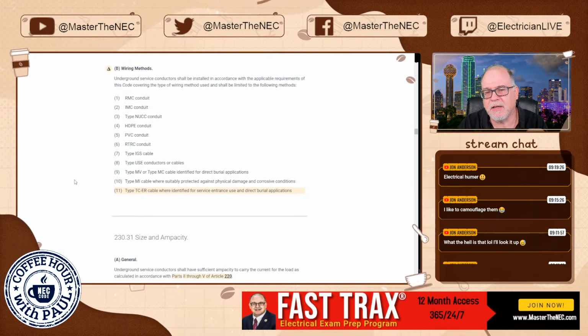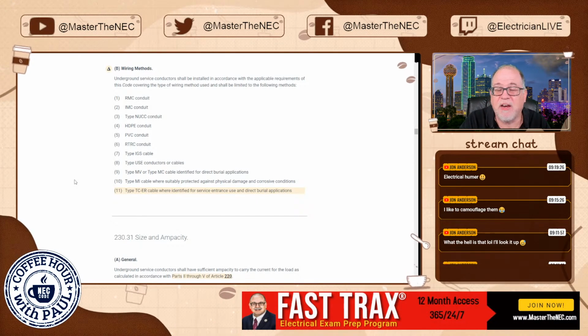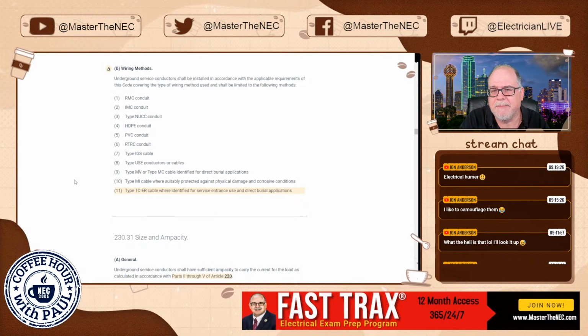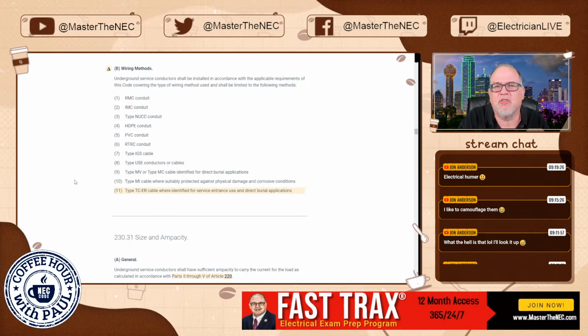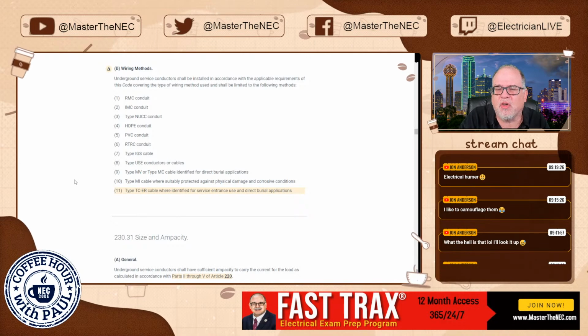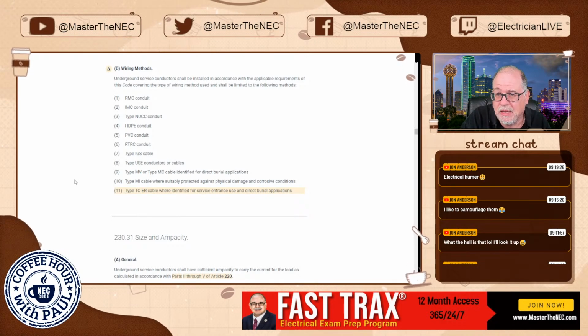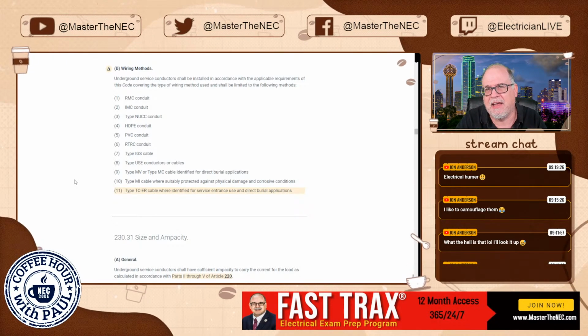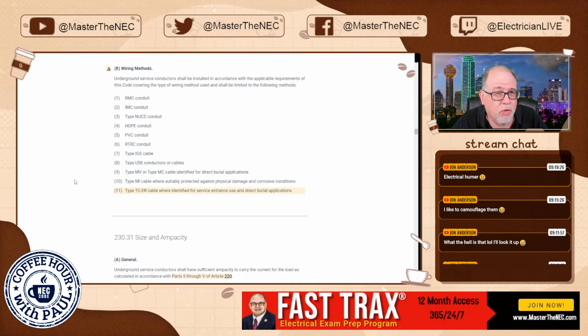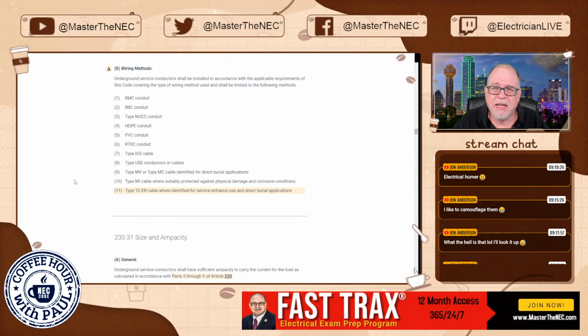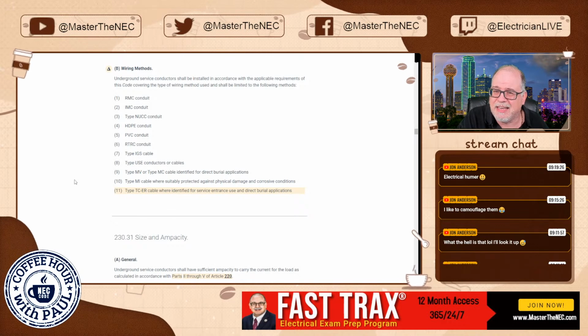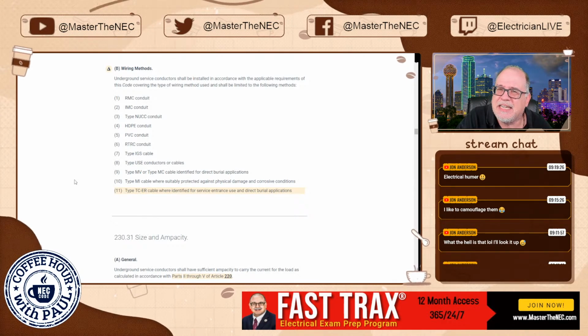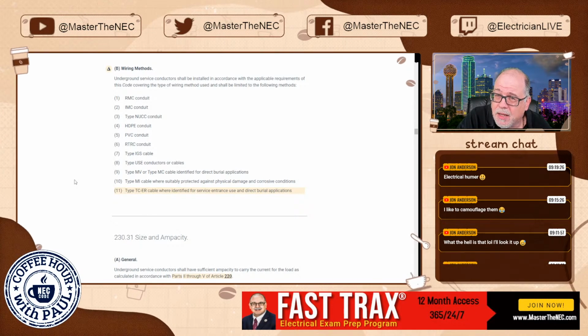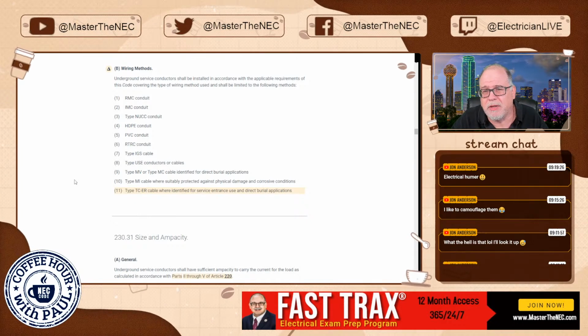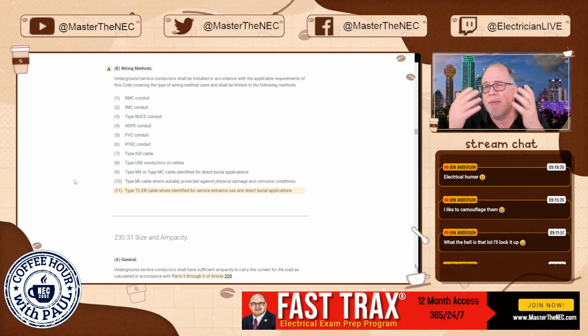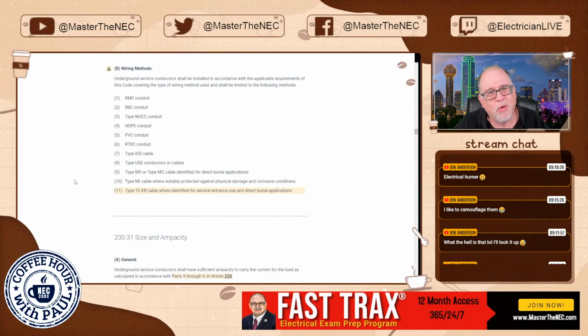And that product is not only TCER JP, joist pull rated, but it also is SER, so it is service entrance use as well, and it's obviously going to have rated for direct burial on it. So the beautiful thing about the hybrid is you can go from in the ground outside and pick up all the properties of TCER with a direct burial rating, but then when you transition into a building, guess what? It magically becomes SER. So what does that mean for you?